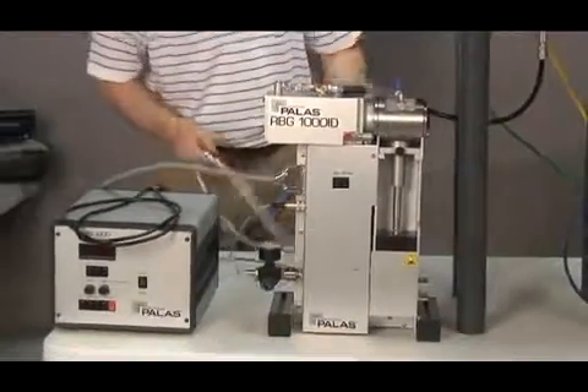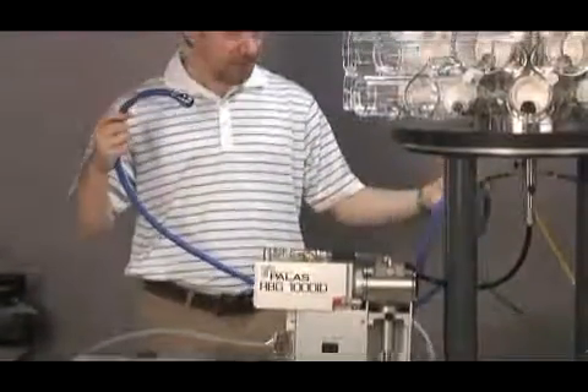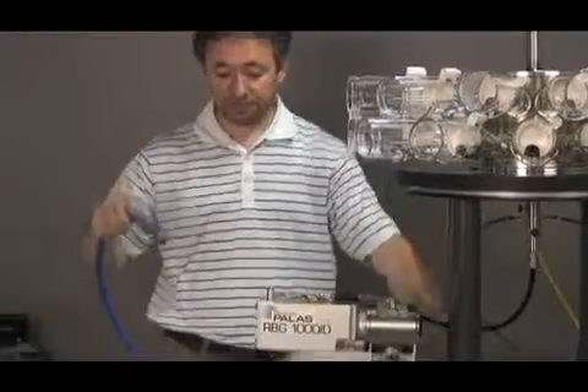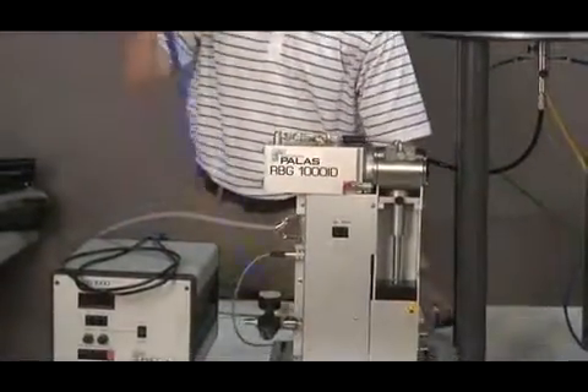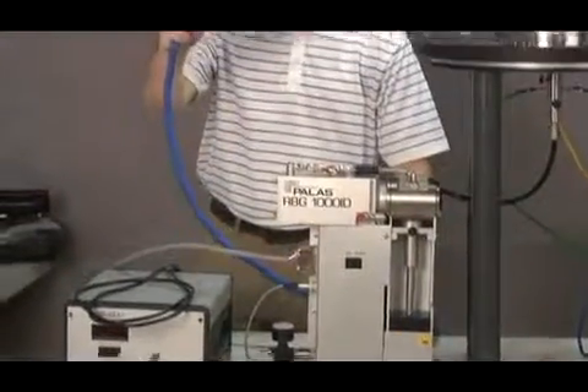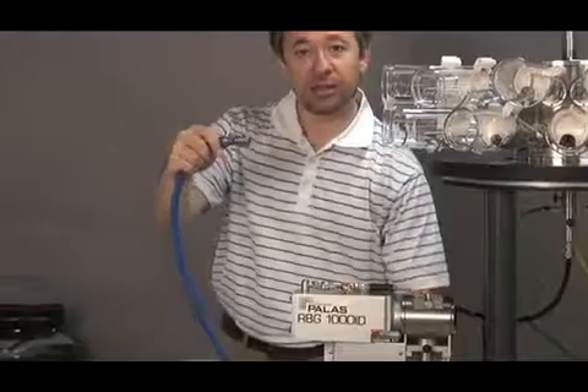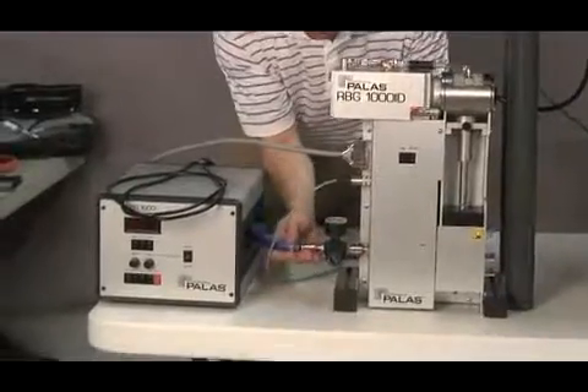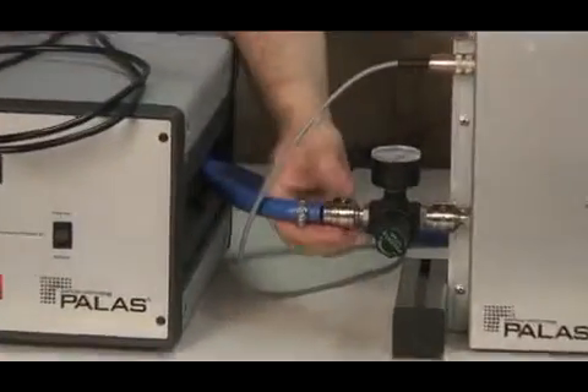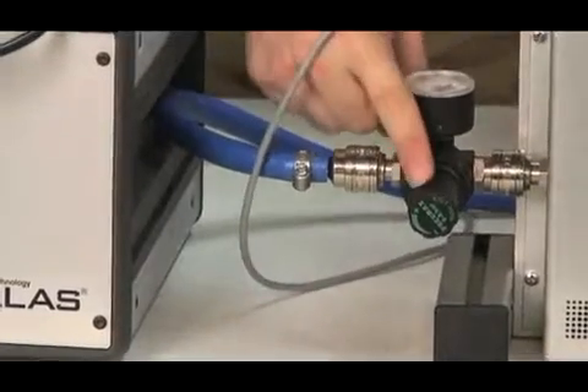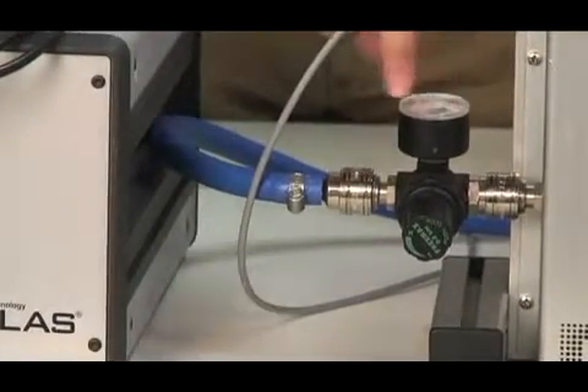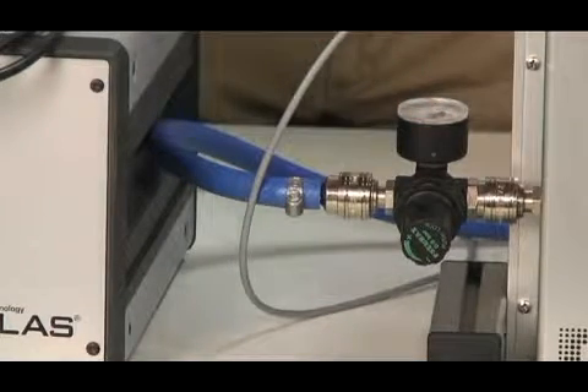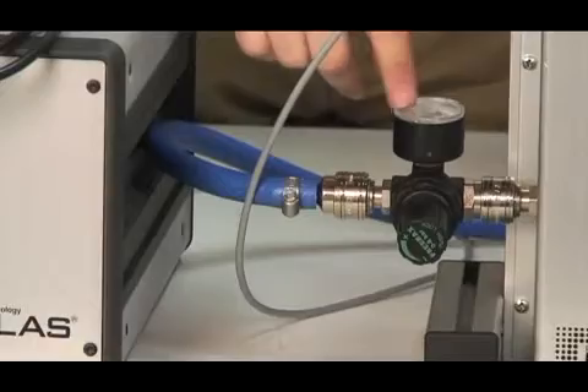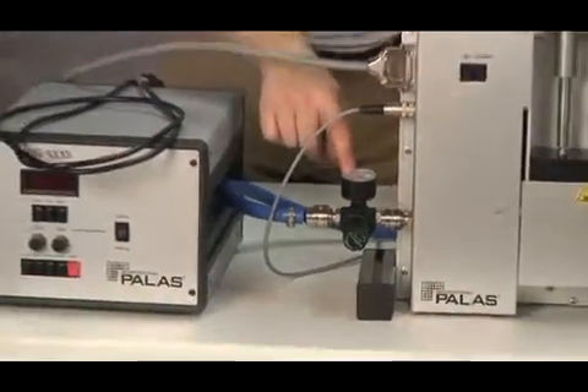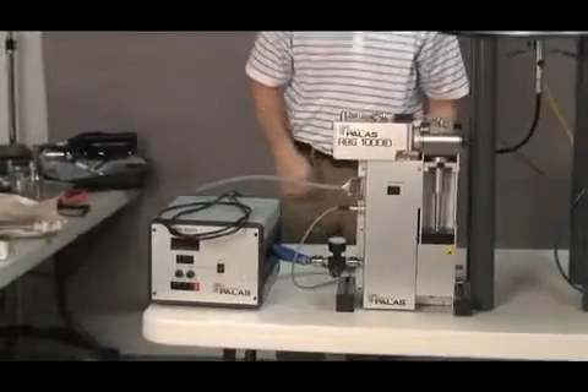The next step will be to connect the deaggregator to the compressed air source. The blue tubing comes with a special female quick disconnect that goes right in. Just push it in until you hear a click. This goes into a pressure regulator, with a pressure gauge that reads the pressure. The RBG can stand up to 3 bars of pressure, and you can see the pressure here on the pressure gauge.